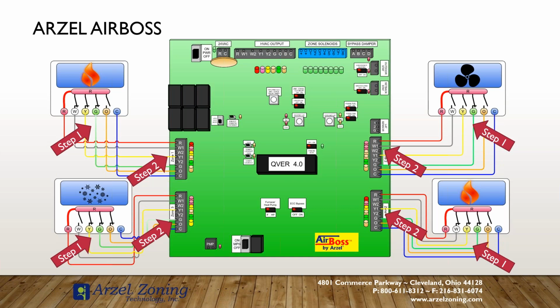All right, so with the Heat Pump Pro, there's individual zone screens that tell you exactly what's being received from the thermostat. With the AirBoss, there's an LED indicator for each of the zone connections. There's LED indicator on the HVAC outputs. So instead of the LCD screen that you have with the Heat Pump Pro, the AirBoss LEDs will tell you what it's doing. So looking at your zone connections, top to bottom, it's red, red, yellow, yellow, green, yellow. That tells you W1, W2, Y1, Y2, G, and O.